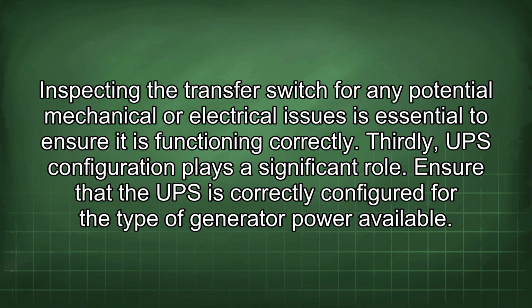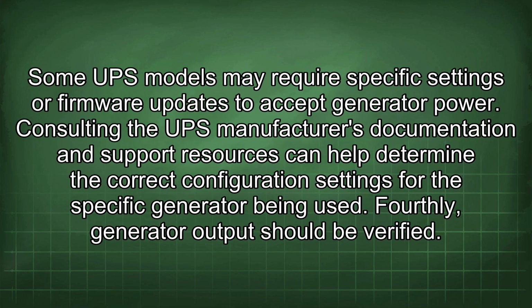Thirdly, UPS configuration plays a significant role. Ensure that the UPS is correctly configured for the type of generator power available. Some UPS models may require specific settings or firmware updates to accept generator power. Consulting the UPS manufacturer's documentation and support resources can help determine the correct configuration settings for the specific generator being used.